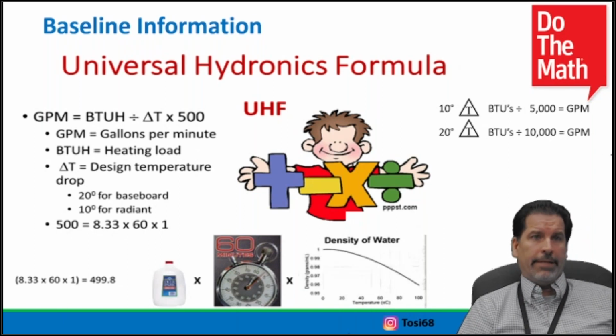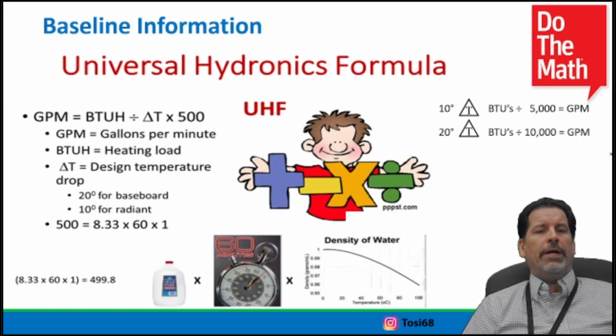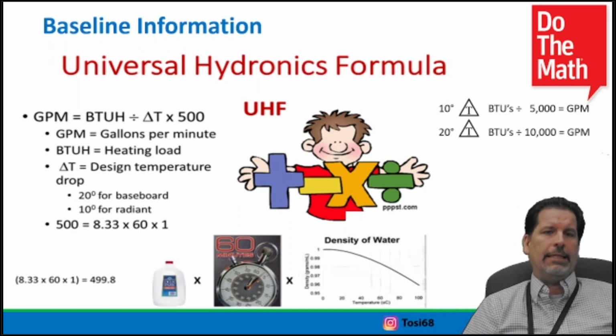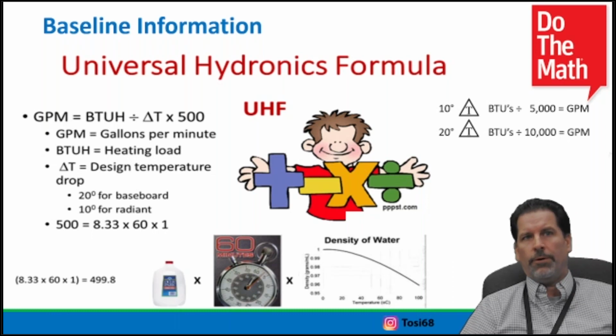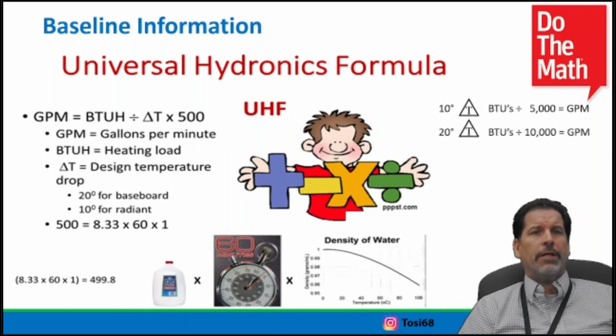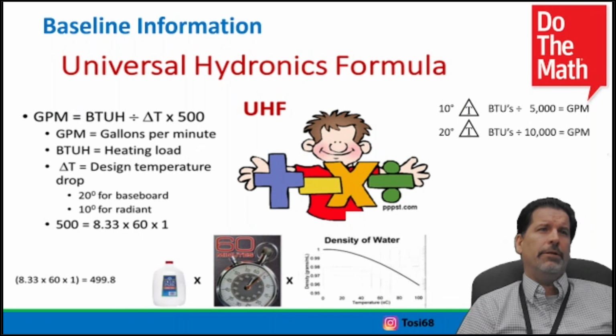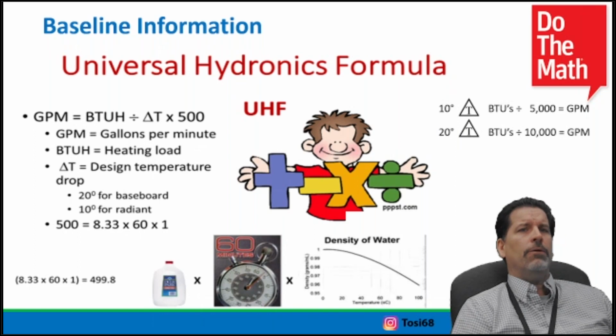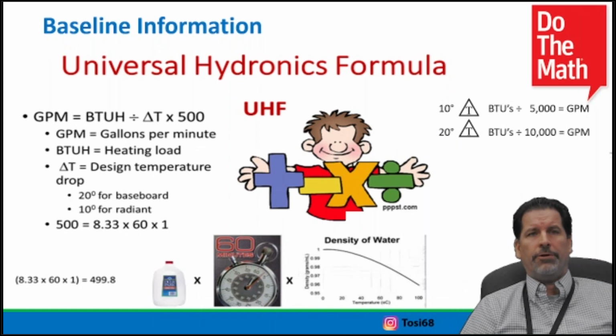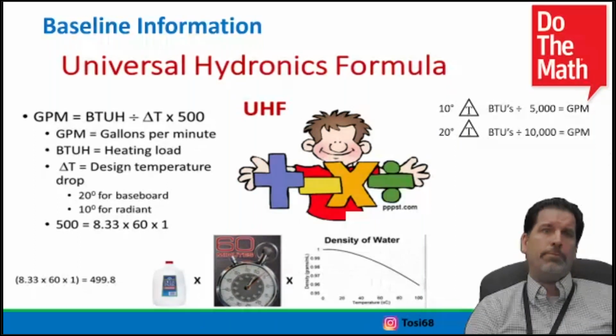Now the delta T, that is our design temperature difference. We have something making the hot water, it's leaving at a certain temperature, it's going out into the home or the building or whatever, and we're leaving the heat energy behind. And that's now the difference of the return water compared to the supply water. So we have systems, typically 10-degree delta T, and we have other systems which are 20-degree delta T. So we can figure out by this simple universal hydronic formula what size pipe we need to install to deliver the BTUs based off of our heat loads.